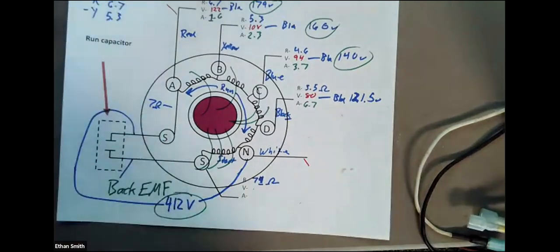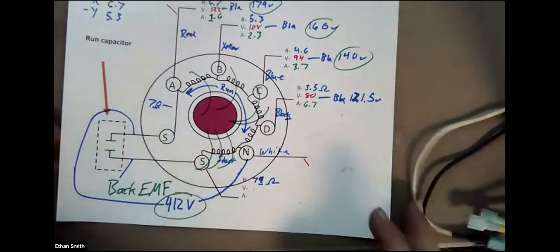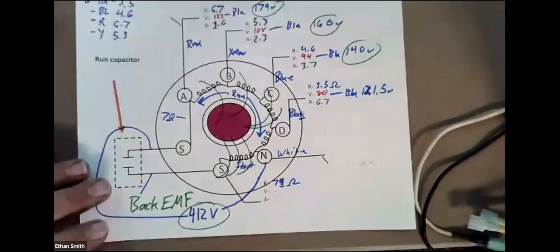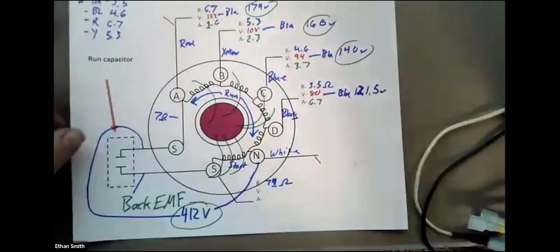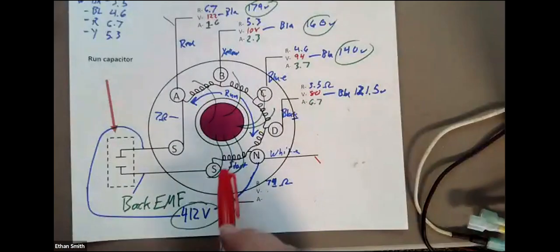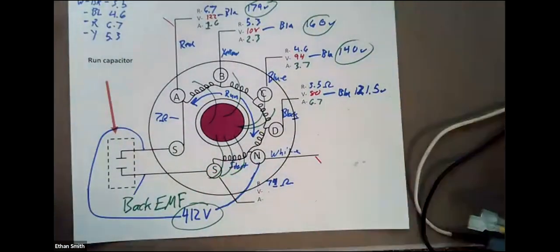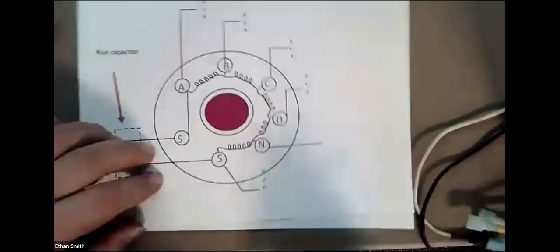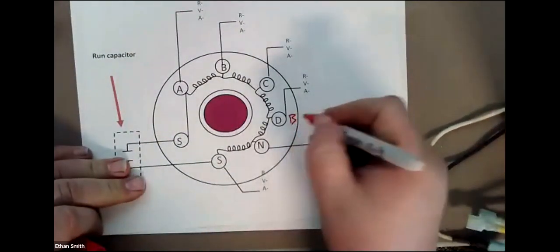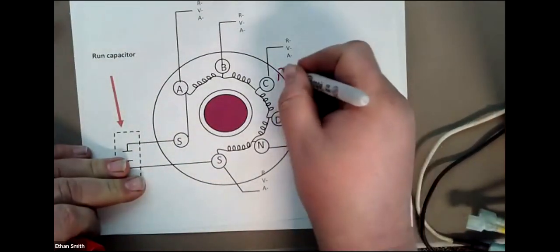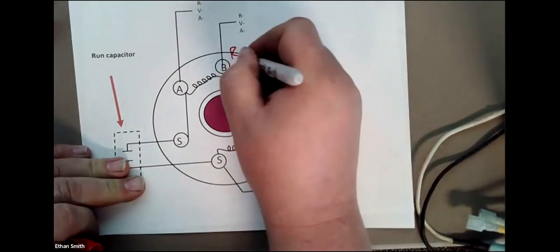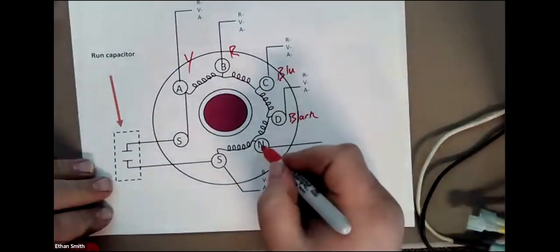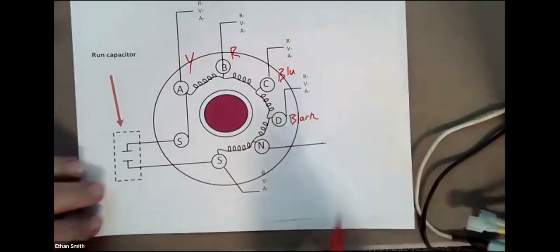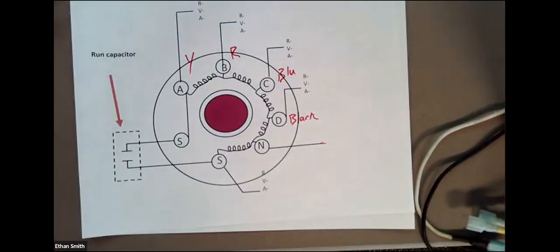So I have a question for you then. Knowing what we know about this motor, we've got our start winding down here. We've done all the analysis that we need. I'm going to pull this out of the way and grab a clean sheet. And we know that's black, blue, red, and yellow, and this is our neutral. What would happen if we used a different terminal for neutral?